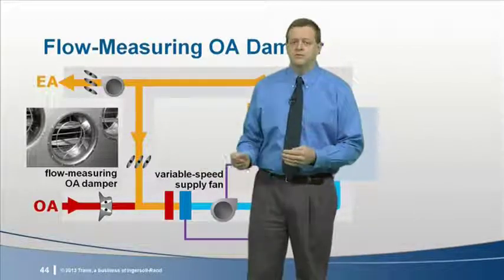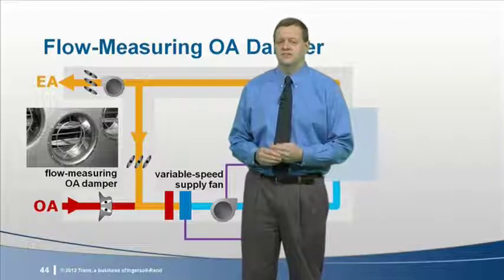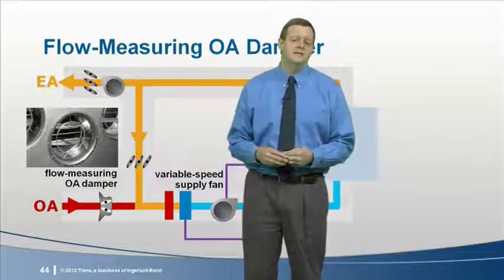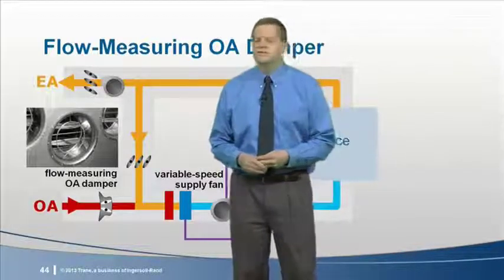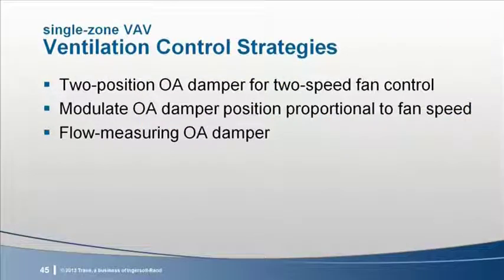However, outdoor airflow measurement does increase the cost of the system, so it's probably more likely to be used in larger systems. These three approaches make sense for a piece of equipment that has a mixing box and an outdoor air damper, such as a packaged rooftop, air handling unit, or a classroom unit ventilator.